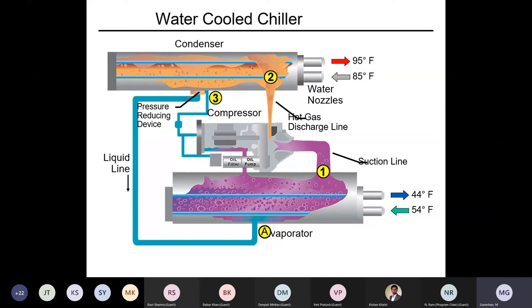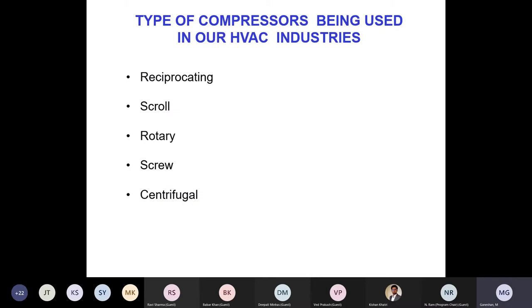Water enters at 54 and leaves at 44 in an evaporator. Same thing in the water cooled condenser: condenser water enters at 85 and leaves at 95. The compressor remains the same. It does the same function over there. So let's see the types of compressors being used in our HVAC industry. We all know reciprocating, the old veterans still going strong in some places, especially in cold rooms and cold storages and many places, including some shipping. Scroll is for all the small ranges, rotary, and screw is medium. We will see what tonnage each can operate. Centrifugal, of course, is for all the bigger installations and bigger requirements.